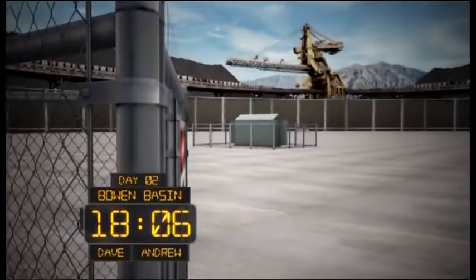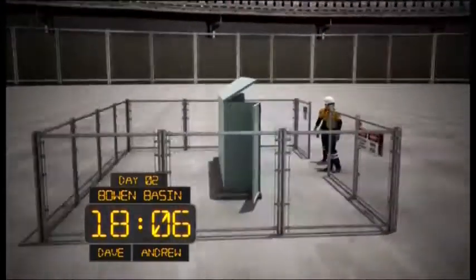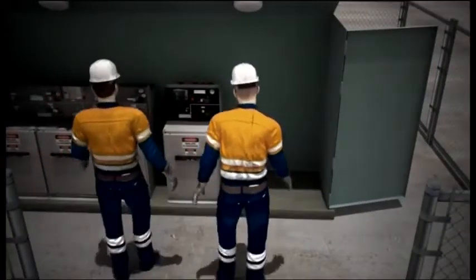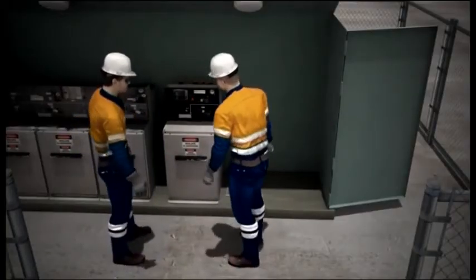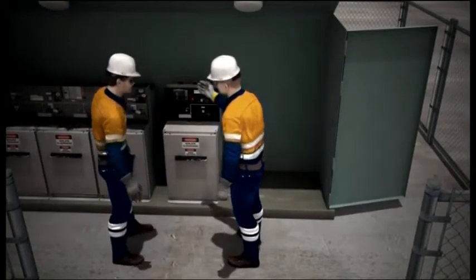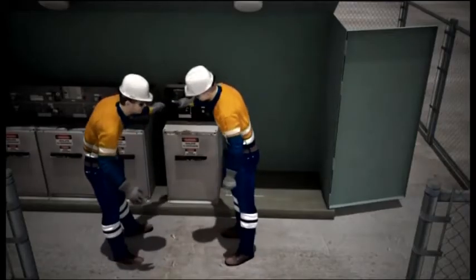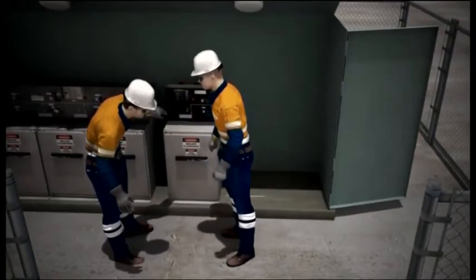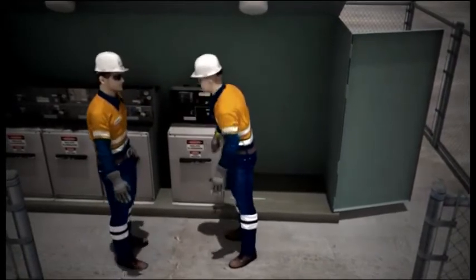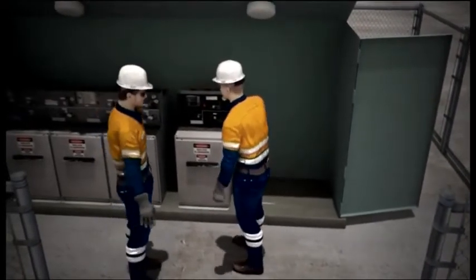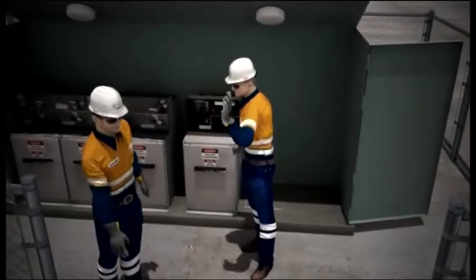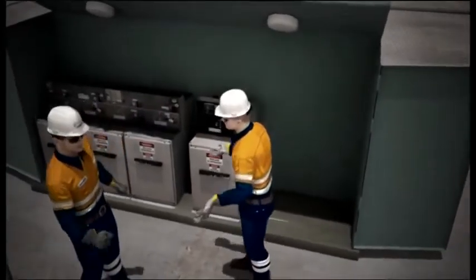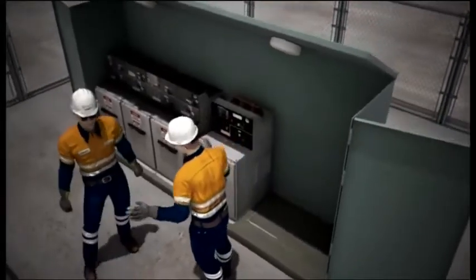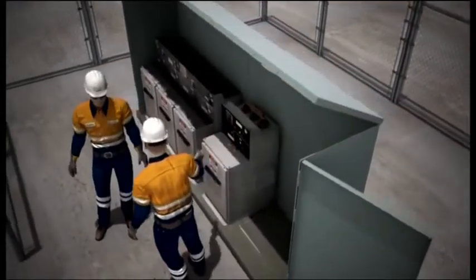During a meal break, the decision is made to remove another mechanism from a third unit at yet another distribution point. This time, however, they decide to lock the springs in place by drilling and tapping some holding bolts into the switch. On arrival, Dave and Andrew hold a verbal take 5 to decide the best course of action for the job. They decide not to apply for an HV access permit, as they believe the job is extra low voltage because they will not be entering a high voltage cabinet.